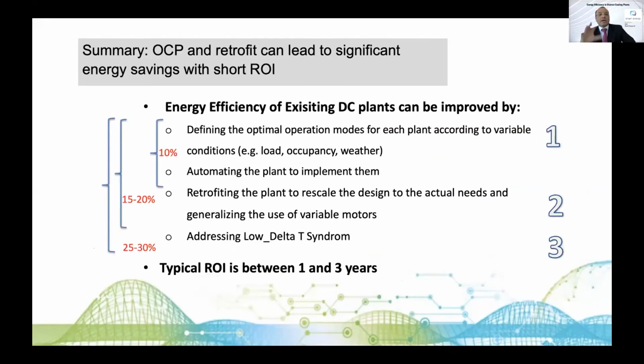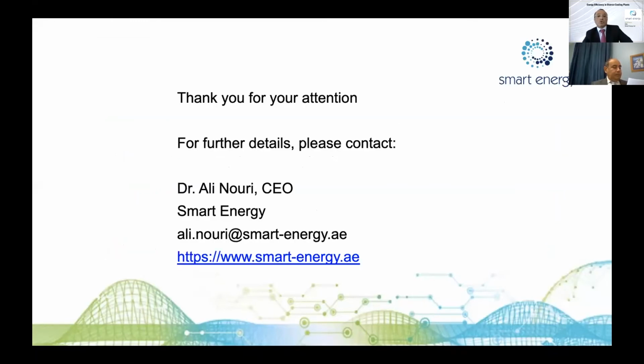So to summarize, here is this three-step strategy: automation and optimum research and optimum calculation of the set points leads to basically 10% of energy savings. Retrofitting and adapting and rescaling the design to the actual needs would lead you to probably 15-20%, and addressing the low delta T would provide you with the optimum to be around 25 to 30% savings. Of course, all this depends on the DCP itself and the maturity of the operation team, but usually ends up with a return on investment of about 1 to 3 years, which is absolutely good. So with this, thank you very much.